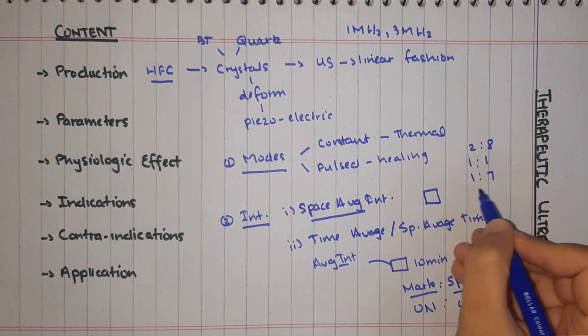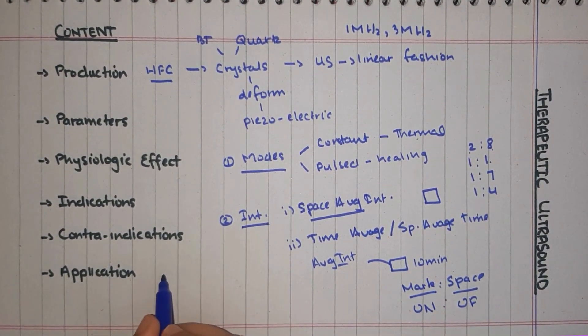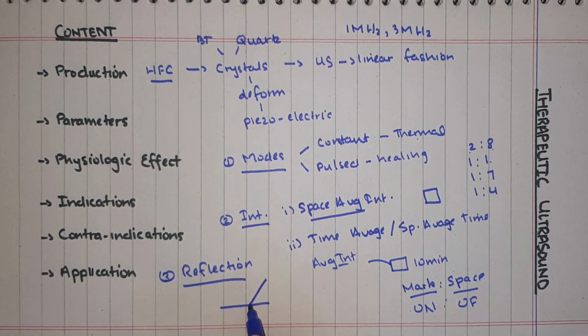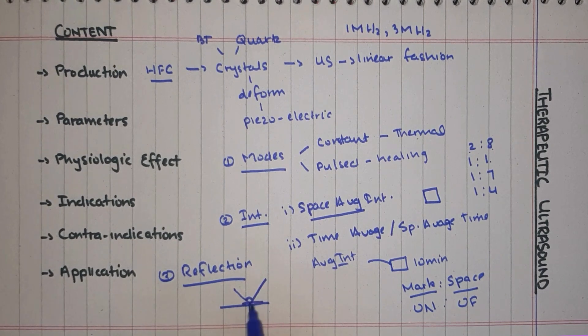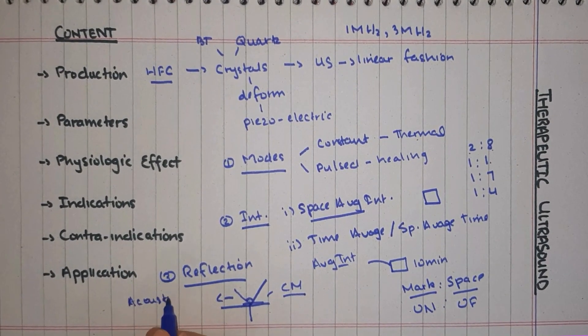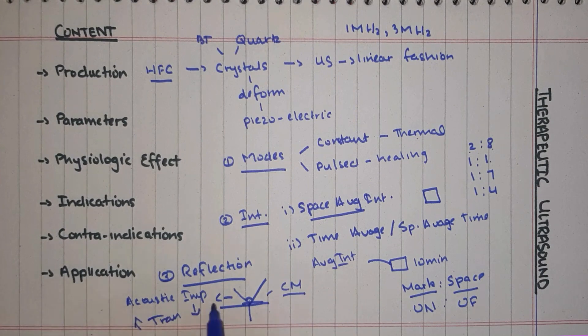The most commonly used mark-space ratios are 2:8, 1:1, 1:7, and 1:4, representing the on and off periods. The third parameter is reflection. When the ultrasonic beam reaches the skin surface, it will partially reflect back. To prevent this reflection and maximize beam penetration, we use a coupling medium, because sound waves cannot pass through air.